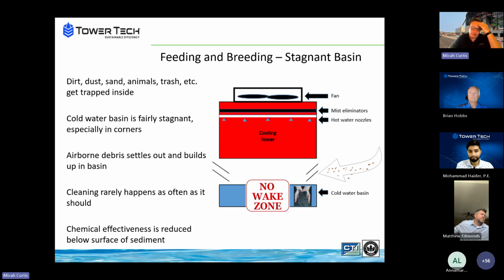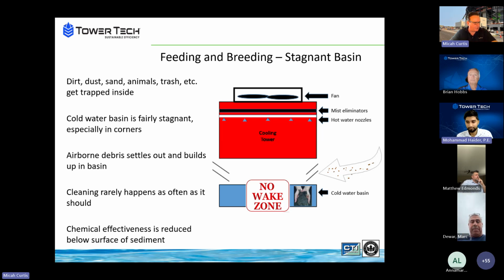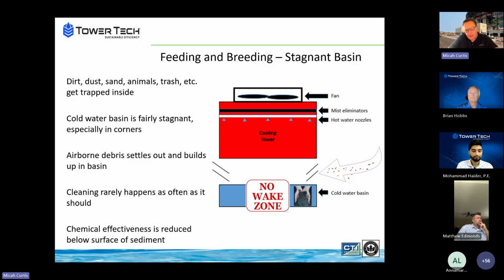Yeah. So my comment on this is I spent the first 15 years of my cooling tower life on the service side of cooling towers, much of it in the southern U.S. And there's a term that is still used called mucking the basin. Real term. And what it meant was one of two things. You drain the basin and you get shovels, and in these corners of these basins, the sediment would usually be stacked up almost to the top of the basin, whether it's a 4, 6, 8, 10 foot basin, or if you kept the water in, you hired a company and they would put on dive gear and they would go vacuum the basin. Almost like a very nasty job. If any of you have watched Dirty Jobs by Mike Rowe, cooling tower basin mucking would be at the top of the list. So a thankless, nasty job and a definite biohazard, especially relative to Legionella bacteria and potential proliferation of that bacteria causing more problems.